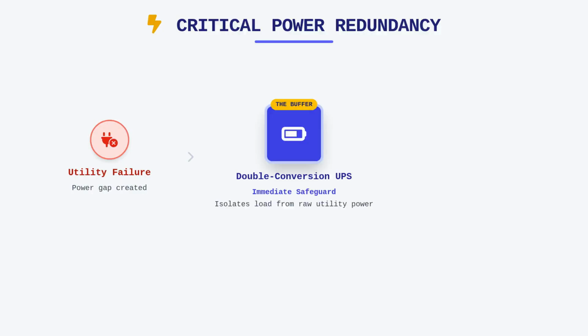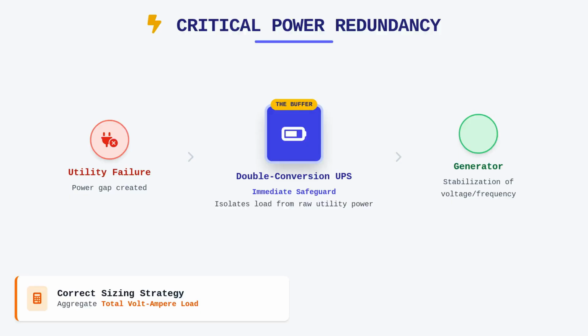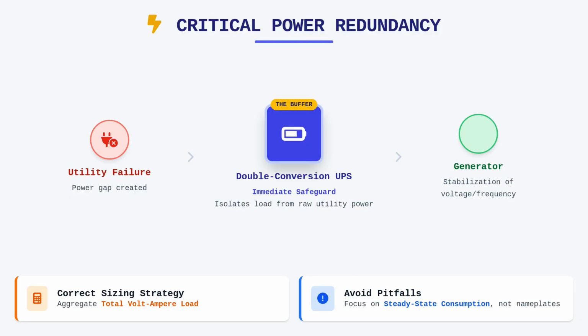An uninterruptible power supply, or UPS, acts as the immediate safeguard, providing clean, conditioned power while the generator climbs to its operational frequency and voltage. To size these systems correctly, you must aggregate the total volt-ampere load of all equipment connected to the critical power distribution units. It is not sufficient to simply sum the nameplate ratings, as this often leads to gross overestimation and inefficient system operation.